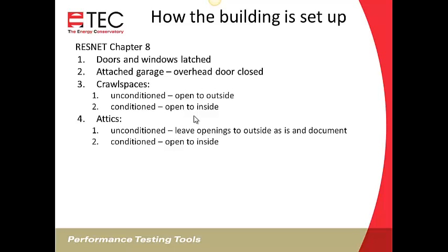Attics, if you've got an unconditioned attic, leave the openings as is and document. So if you've got an unconditioned attic and it has a window in it and that window is open, you want to document that. You don't want to change it. But if you document that, if somebody else goes back to that house and does the test and that window was closed, you may get different results depending on how much venting that attic has. And so we want that test to be repeatable, so we want to set it up in the same conditions.